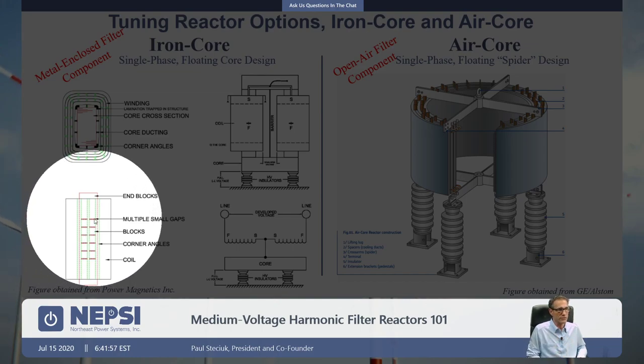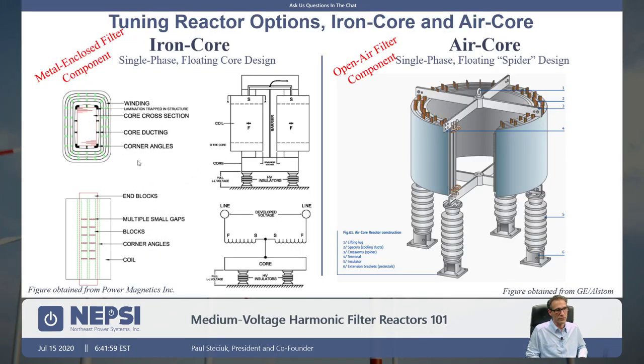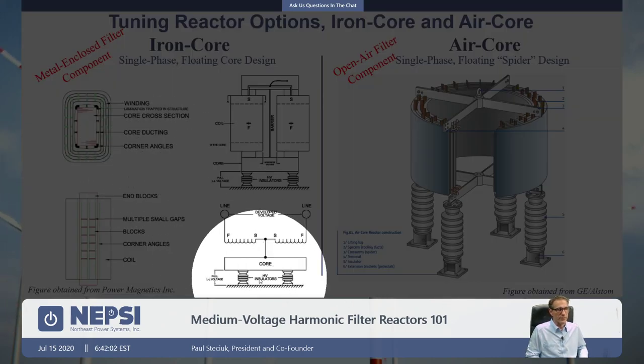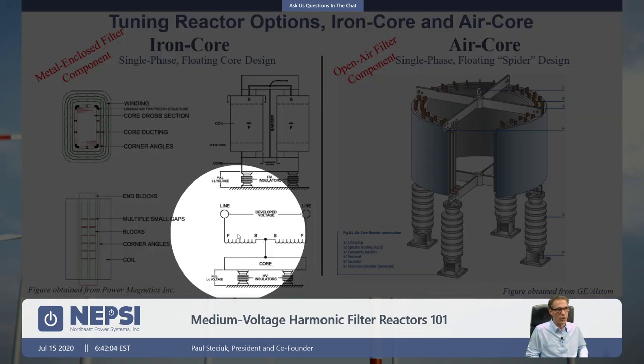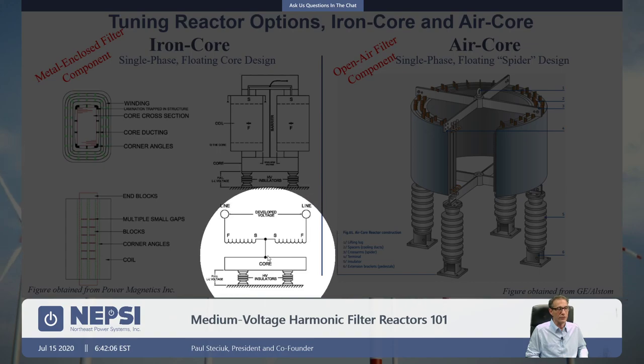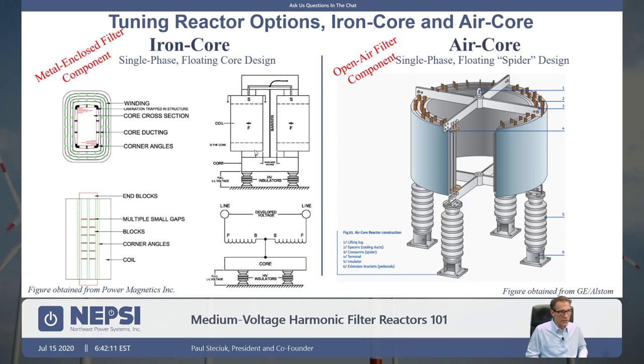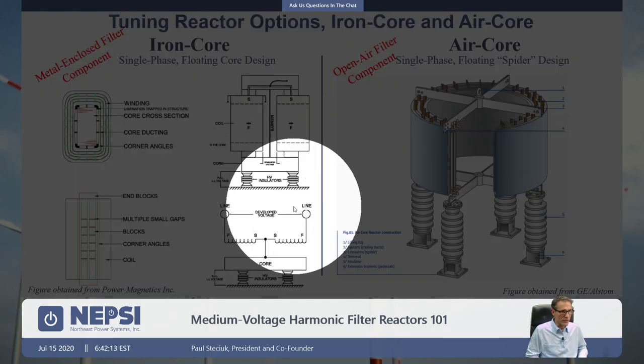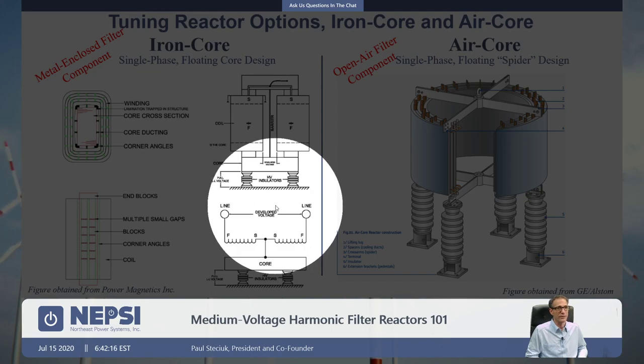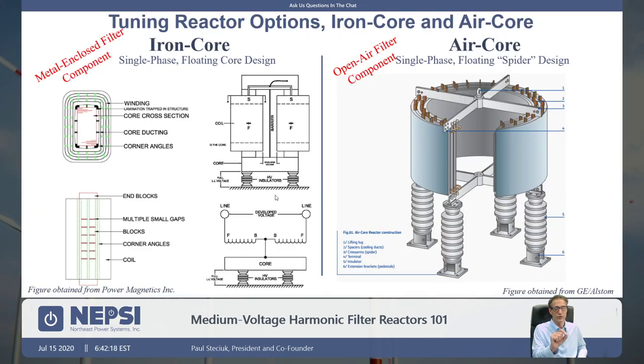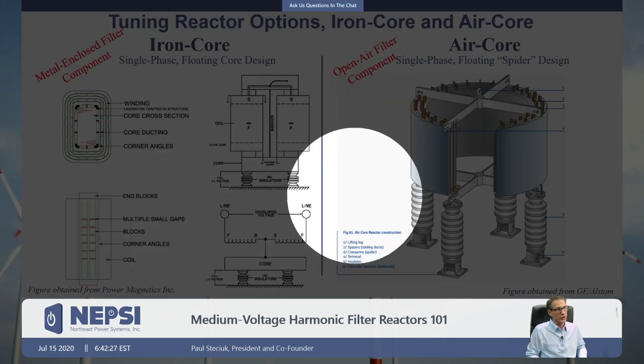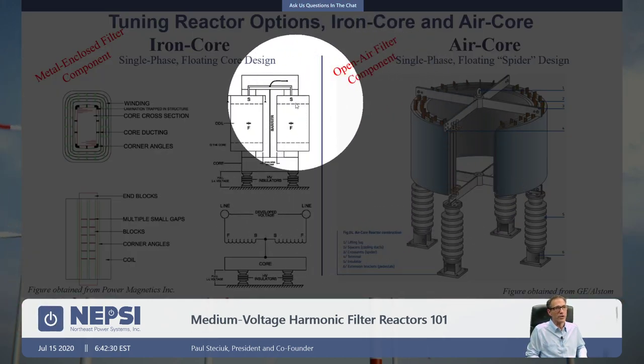Single-phase reactors are put up on insulators and the winding is tacked to the core, so the whole core and supporting structure are elevated in voltage. We do that because the voltage drop across a filter reactor is generally 1 over N-squared times the line-to-neutral voltage. The air core reactor has a lot of similarities to iron core reactors. The winding is spun around a spindle — the spindle supports the winding the way the iron does in an iron core reactor — except we've removed the iron.